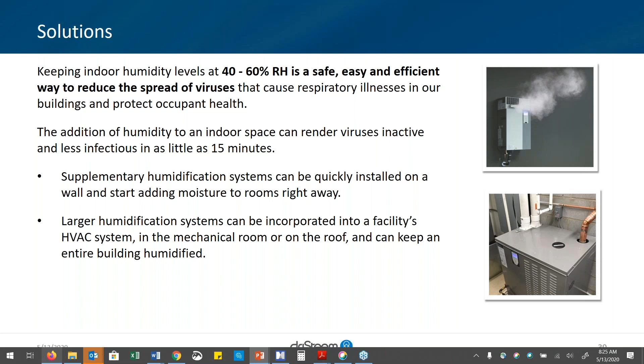We recommend that any strategy start with a site survey. Most healthcare facilities were commissioned with humidification, but this equipment may not be operating due to maintenance issues, may have been turned off, or the humidification levels reduced. Taking RH readings using a hygrometer, or checking levels via the BMS in areas that may experience COVID cases or asymptomatic cases, will quickly determine if a facility is optimizing its defense against the virus. A target of 45% RH is generally recognized as providing positive benefits.